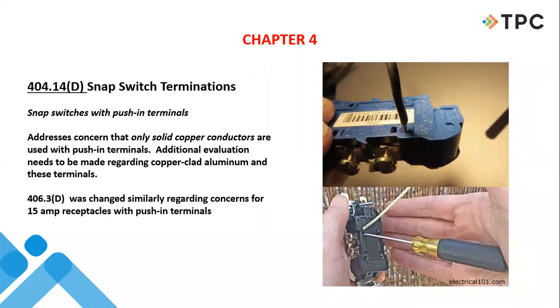406.3D was changed similarly regarding concerns for 15 amp receptacles with push-in terminals. You get quite a mixed bag of feelings throughout the industry regarding people's approval or lack thereof of these snap locks or stab lock receptacles. There's no denying that they're quick, but I think this is a step in the right direction regarding, look, if we're going to use them, let's make sure that we use them with certain products for which they're much better suited.